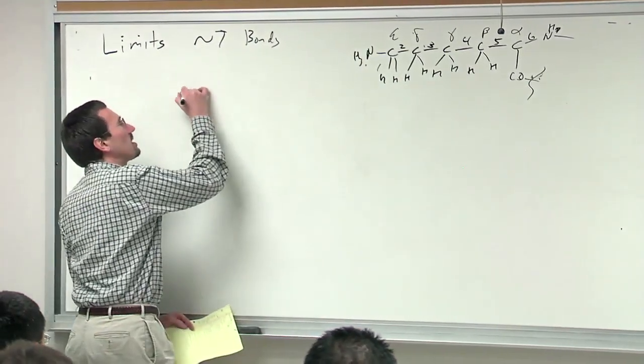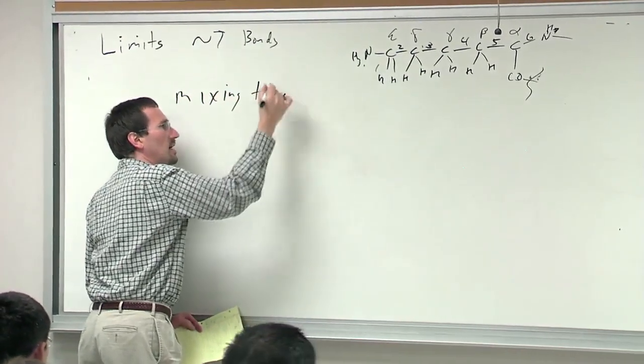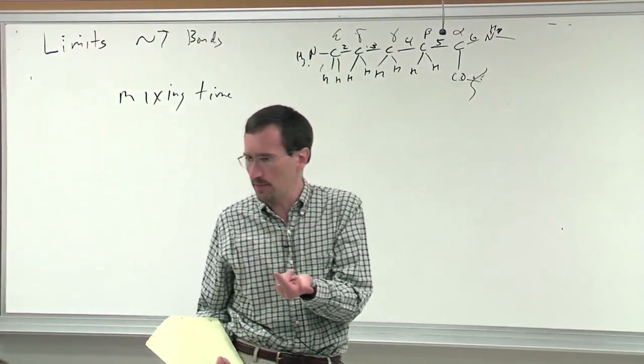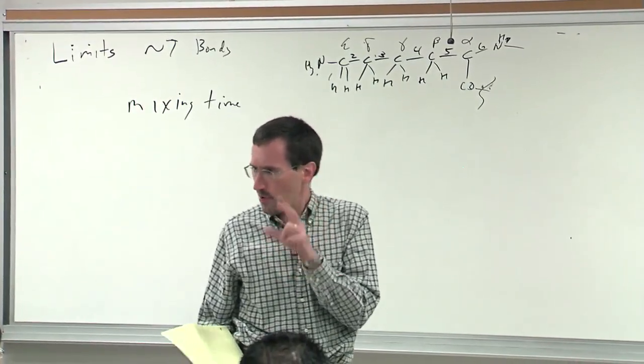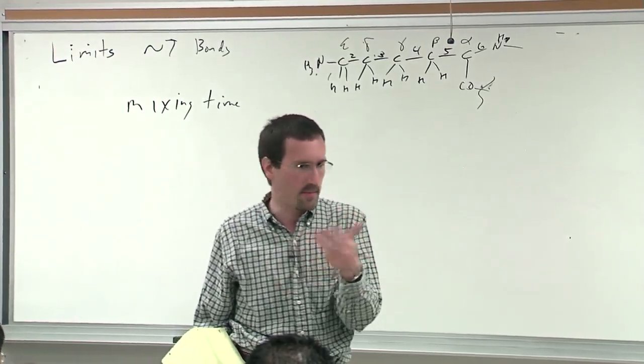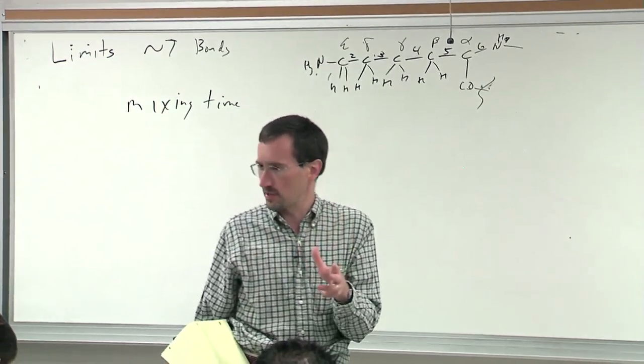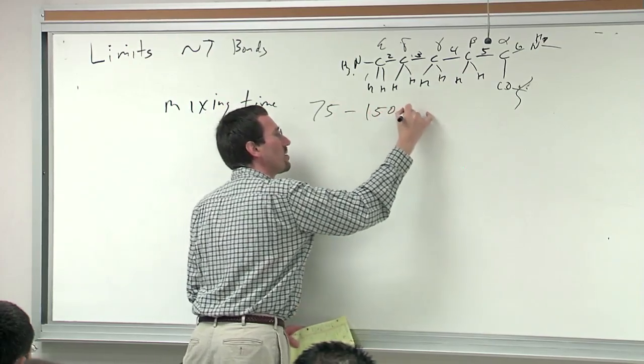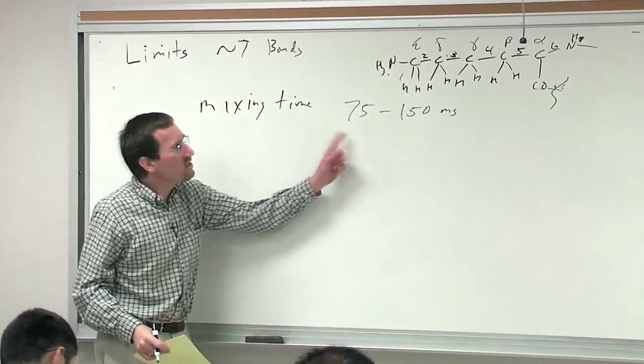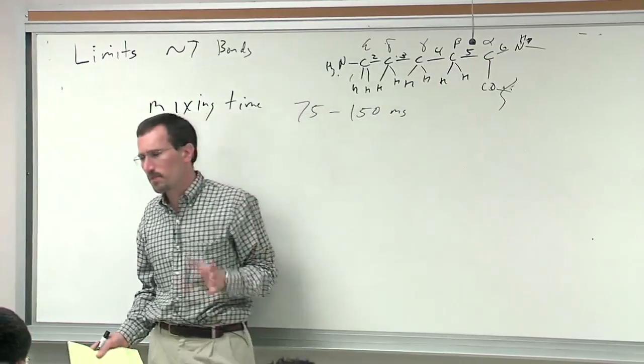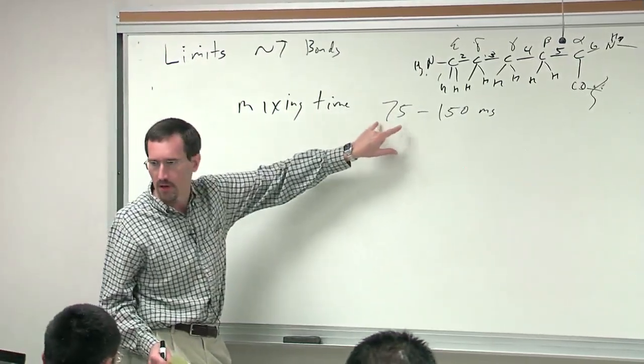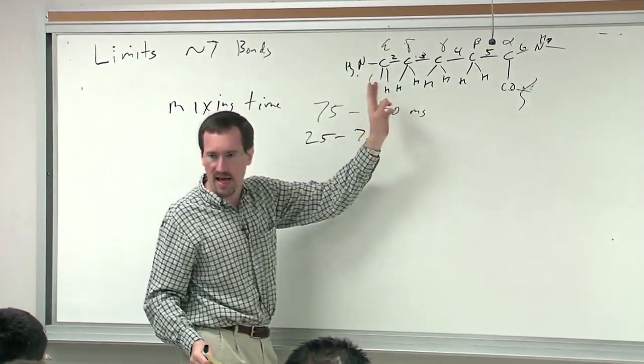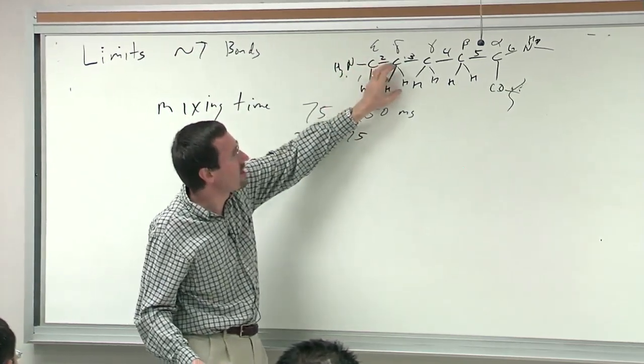The key parameter is the mixing time. Unlike a COSY or HMQC where the default parameters work as one-size-fits-all, in a TOCSY experiment you actually have to think intelligently. Typical values are about 75 to 150 millisecond spin lock mixing time — you'd want to go to the high end to pick up longer correlations, up to say 200 milliseconds. If you go shorter, say 25 to 75 milliseconds, you'll be using it as a super COSY walking from one bond to the next.